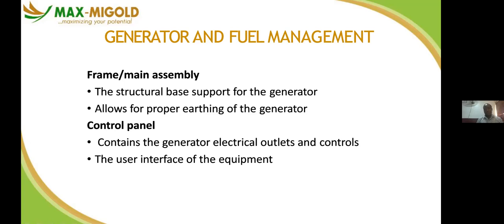You have the control panel. It contains the generator electrical outlet and controls the user interface of the equipment. This is where you communicate with your generator, your user interface. These are the panels that indicate the error, the fault, and the operation of it. It has the history of your generator: the number of times you started it, the number of times it has shut down, the number of times you have overloaded, and so on. So the electronic panel helps you to keep a record of it. It's like your computer. It has software where all the information you are looking for can be gotten or generated.